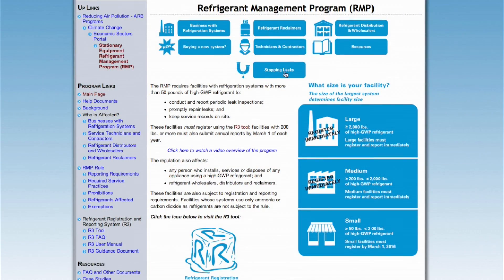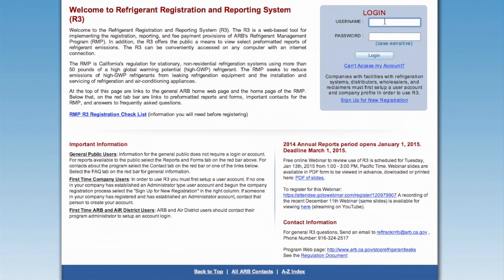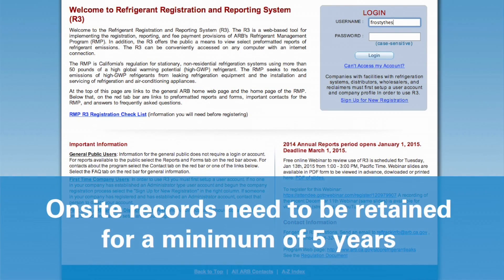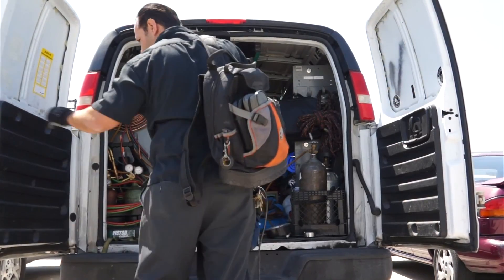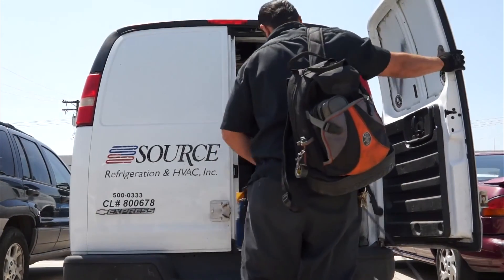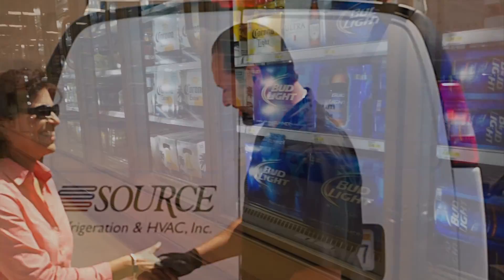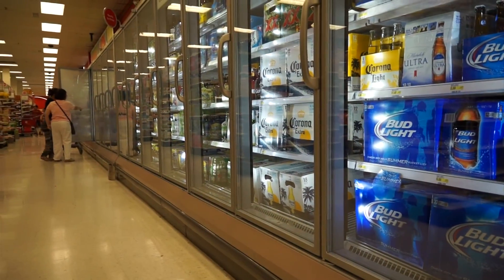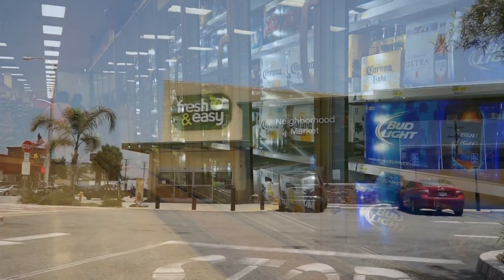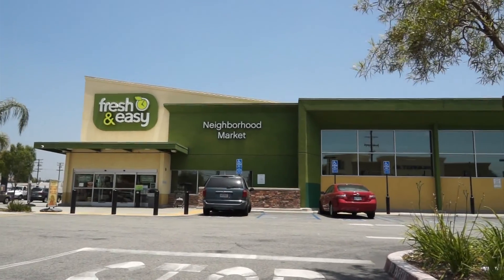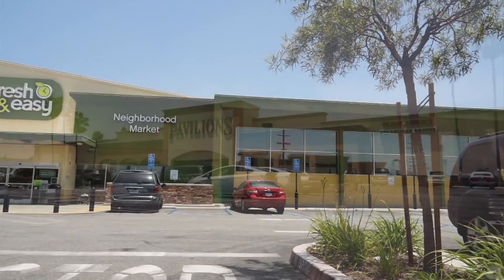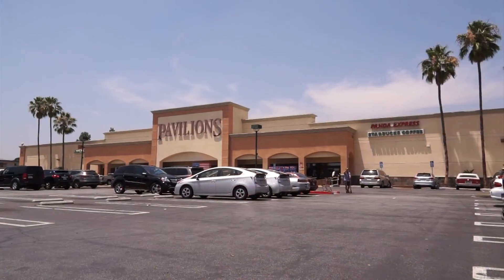To complete the leak inspection, maintain proper records and be sure to input the results into the California R3 database annually. Remember that on-site records need to be retained for a minimum of five years. While not required by law, it is recommended that leak checks be performed by an EPA-certified technician. Thank you for doing your part to help reduce the impact of greenhouse gases on the environment by preventing leaks. In the long run, you will be reducing costs through early detection.